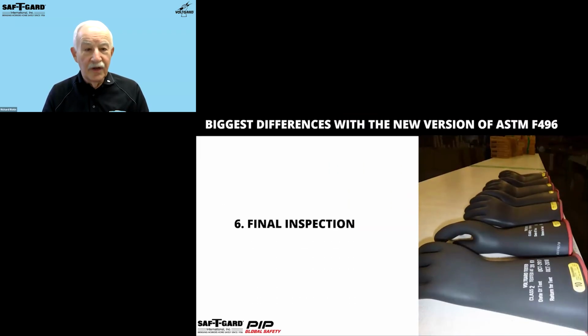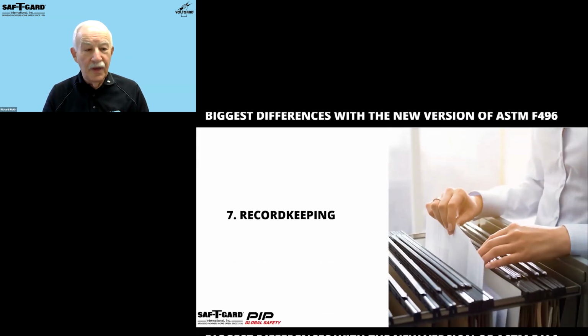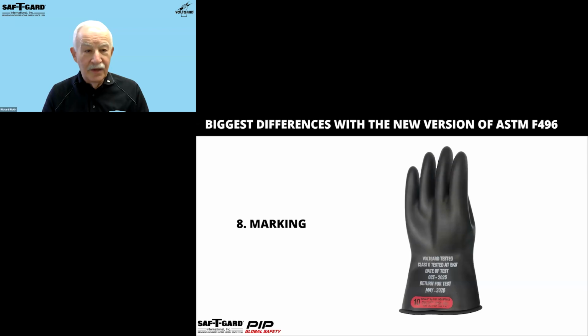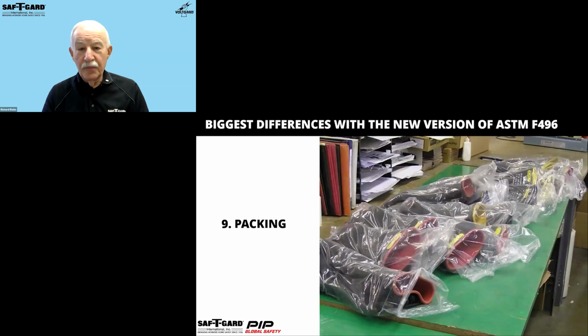After final testing, there's a final inspection of the product with some necessary record keeping, marking as recommended to indicate the date of test and a return for test date. Careful packing for return shipment in appropriate containers, meaning boxes or similar sturdy packaging materials to prevent folding, creasing, or other loose storage that can cause stress on the rubber for storage or shipment.